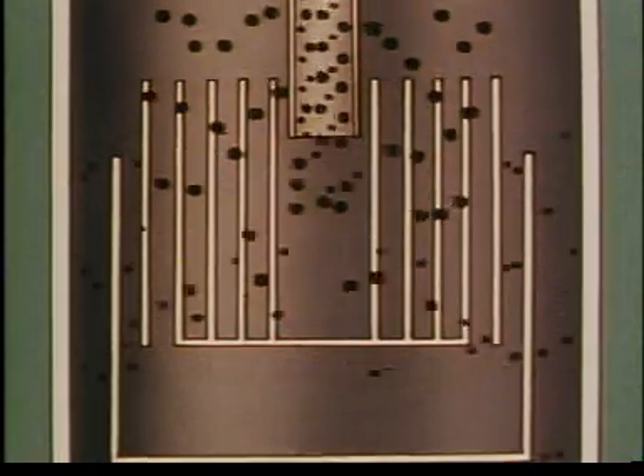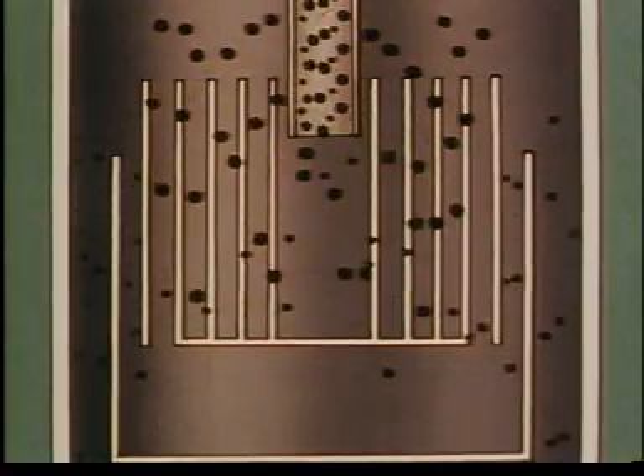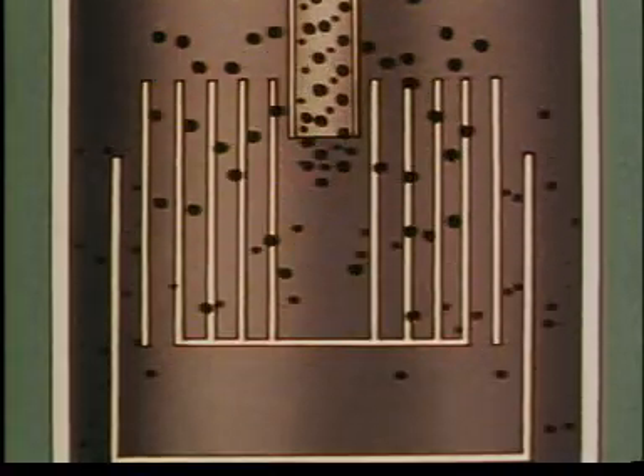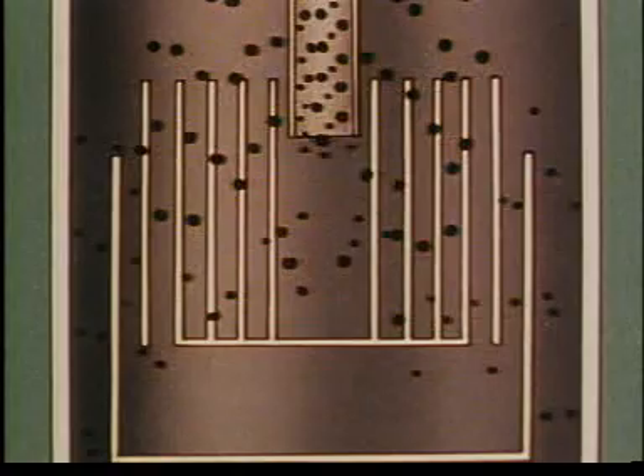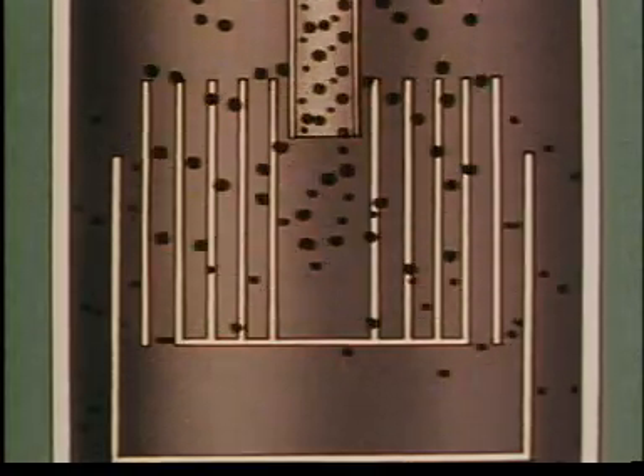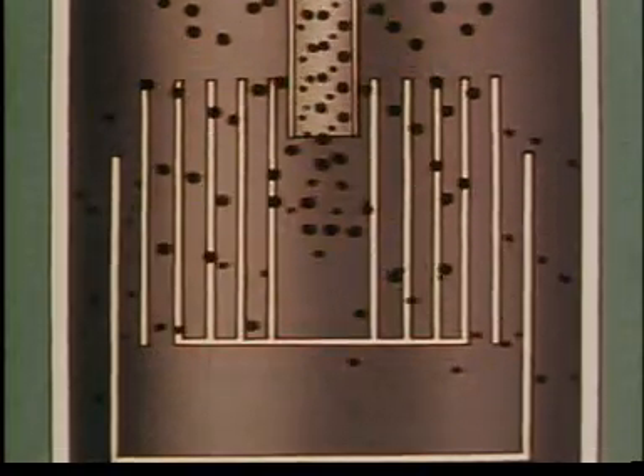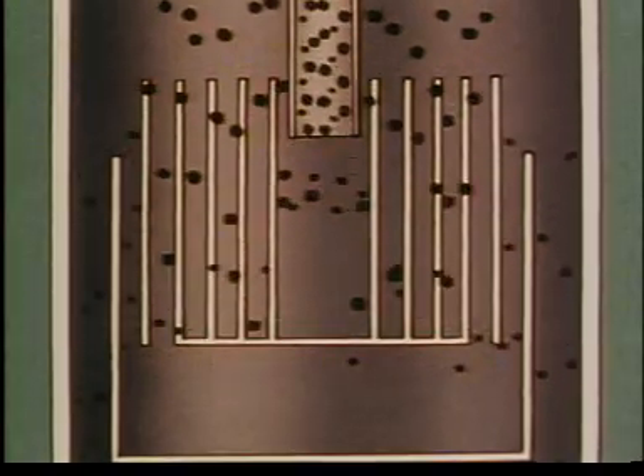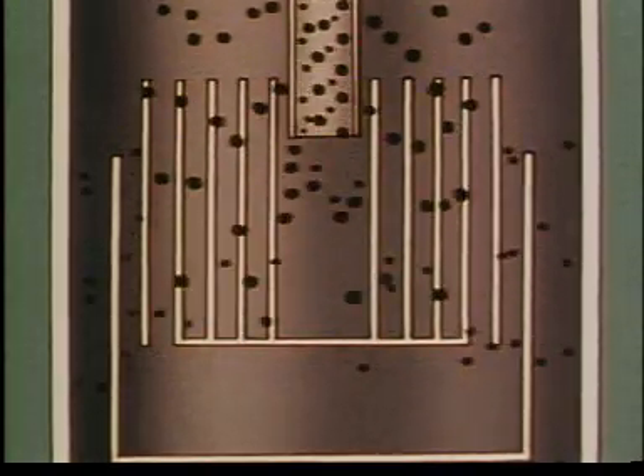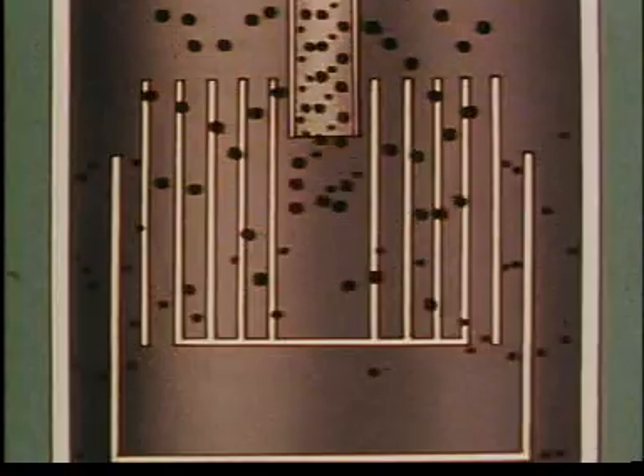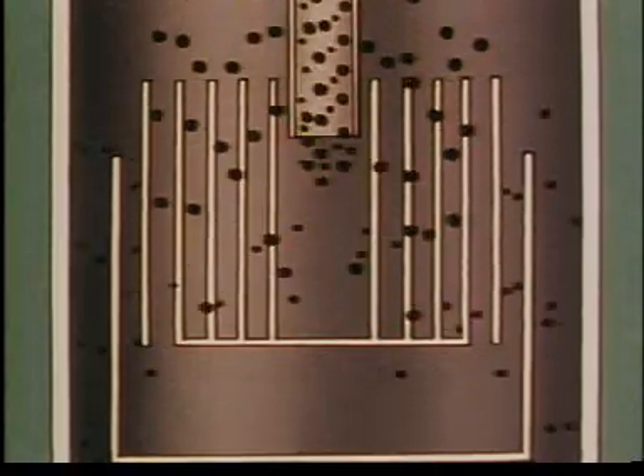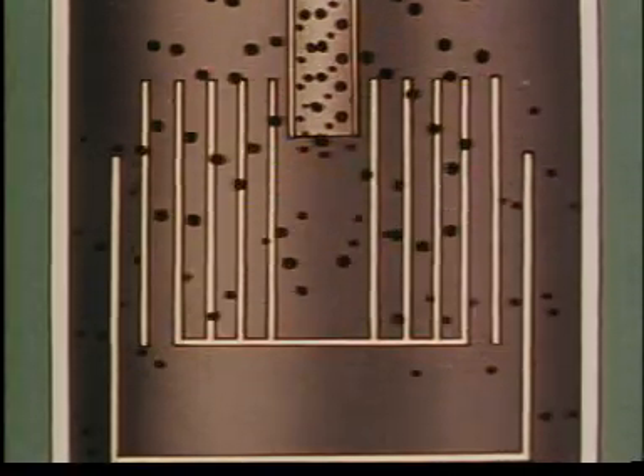Here is a diagram of how the separator works. The water, mixed with large and small globules of oil, flows rapidly down the entry pipe into the center of the spiral ducts. Here it immediately slows down, and the large globules start to separate out, rising upwards through the open tops of the spiral ducts. By the time the water has emerged from the ends of these ducts, most of the large globules have floated upwards.